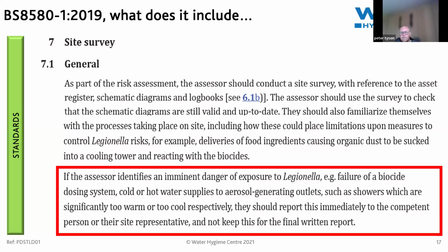After that desktop appraisal, there's a need to look at the risk systems within the property, physically go and check these things: take temperatures, look at flow rates, dead legs, areas of concern. This requires the assessor to look at the current asset list, visit that item, device and system, and assess it. It's not a drive-by. It's not a cut-and-paste approach to risk assessments, saying we've done it before so it's just a quick look at the survey.